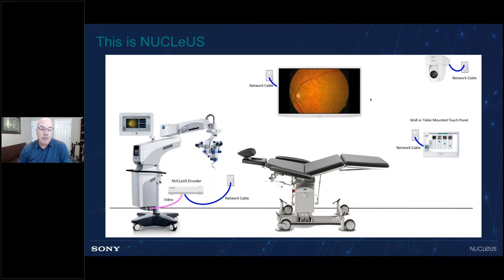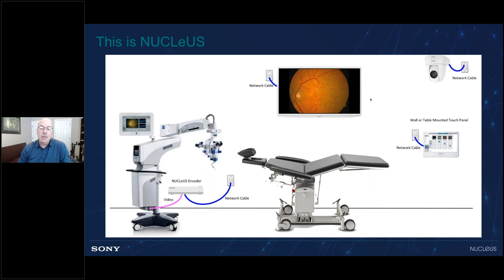Our user interface touch panel is right there on the right. The encoder, or IPC as we call it, ingests the video signal and puts it on the IP network. It's connected to each video modality, and a similar IPC or decoder is connected to each display. We have a special VESA mount for the IPC on the display, so it fits neatly between the display and the mounting bracket. That touch panel controls the entire system. It can start and stop the capture of an intervention, switch the right image to the right display, initiate a timeout, and broadcast any source to a remote viewer.